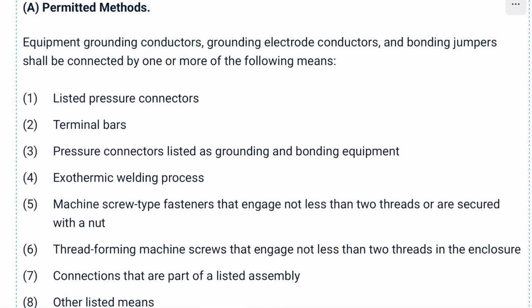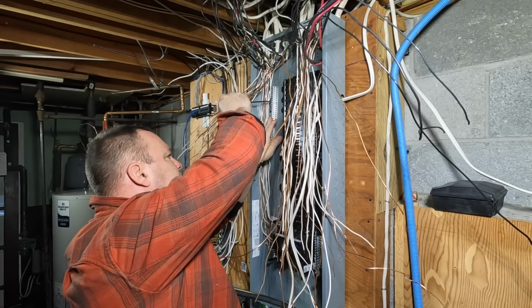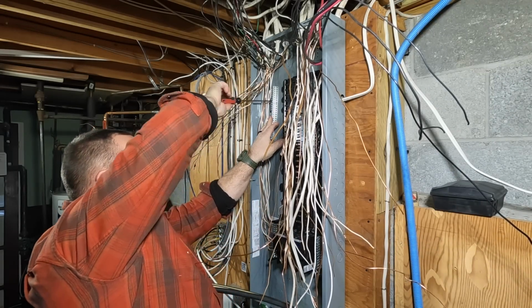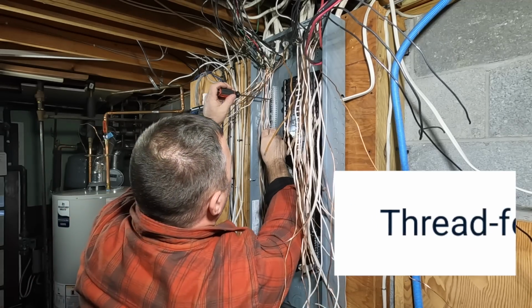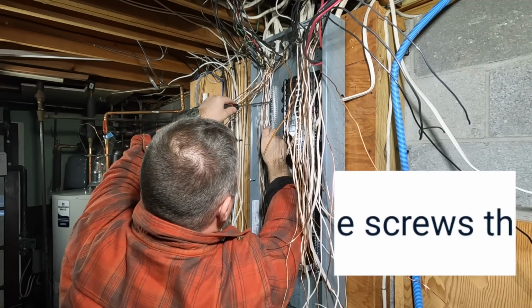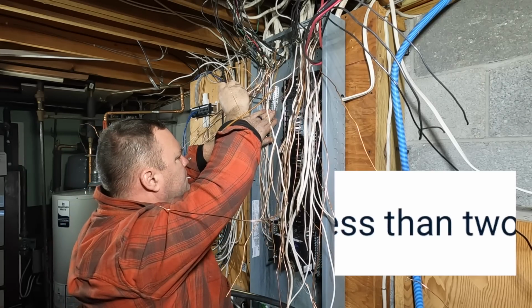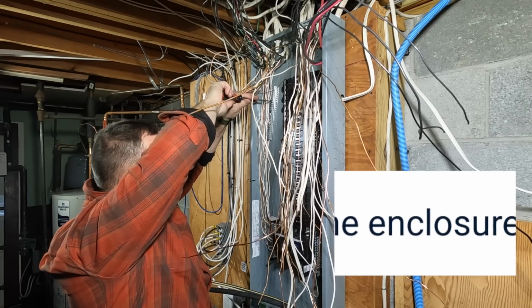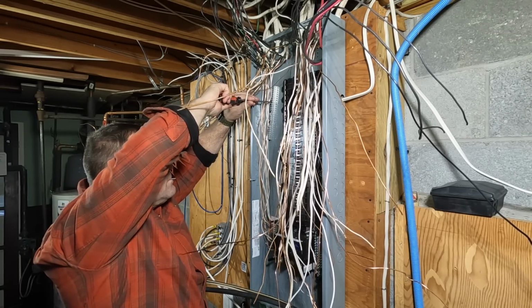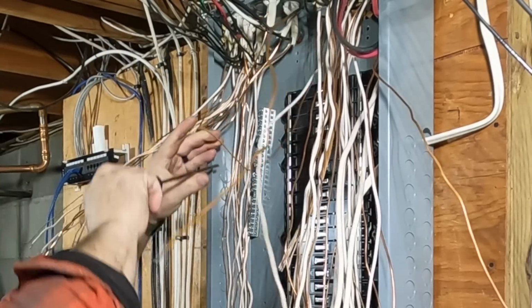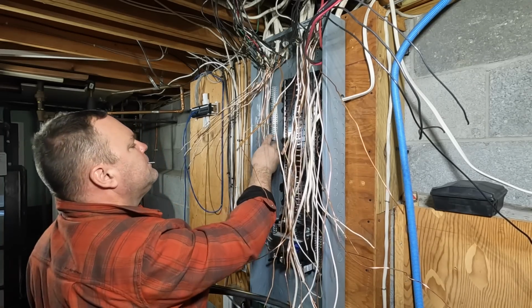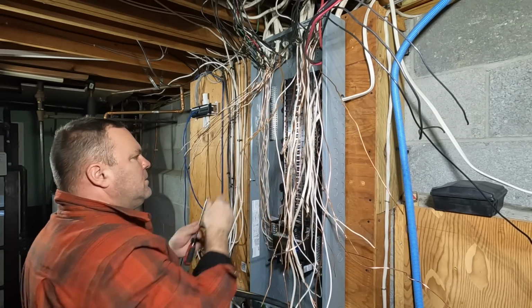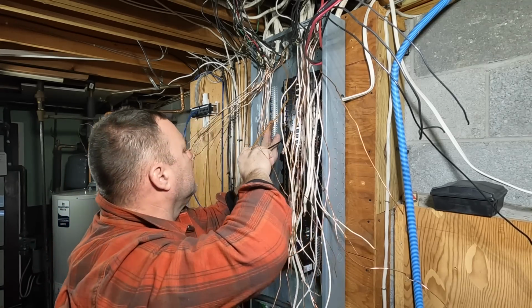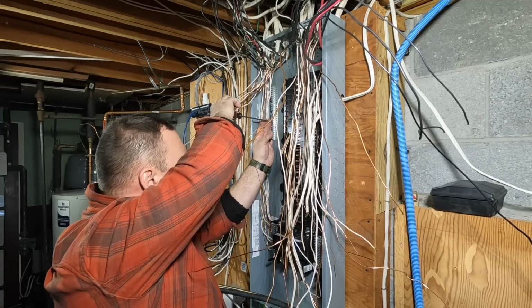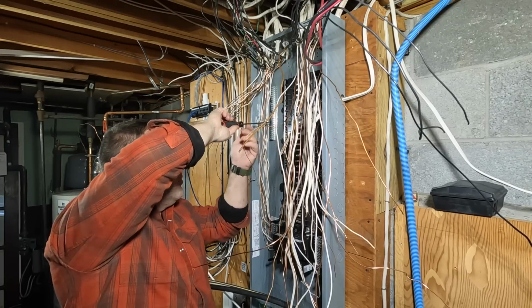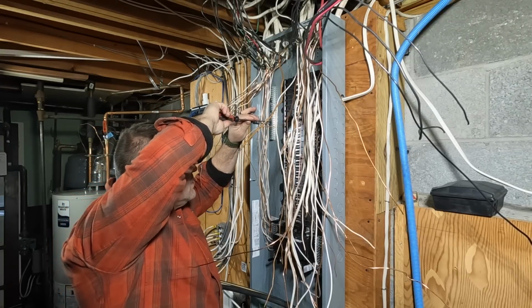Okay. Once they get this in there, it'll be engaged with the 2 screws, and I'll put that section up on the video so you can find out where that section in the code is. I'll have to find it right now. I think it's in Article 200. There's one that's in. There's another. And then, like I said, what I'm going to do is run a jumper. I'm going to add some lugs. I'm going to run a piece of number 4. I should have that in my truck, I hope.